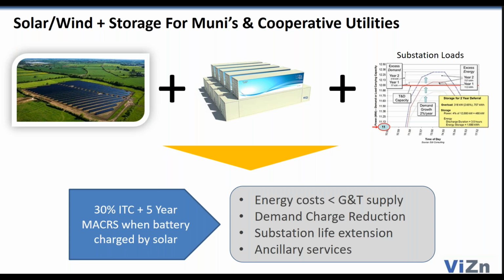They buy their power and they pay demand charges. A big storage market in California is commercial and industrial demand charge reduction. Well, it turns out munis and co-ops also pay demand charges, and they typically own their substation. Those substations can or can't be reaching the end of their useful life, and often there's an expectation for when that substation is no longer going to be able to meet its capacity due to load growth. Frankly, these entities can't monetize the tax credit.